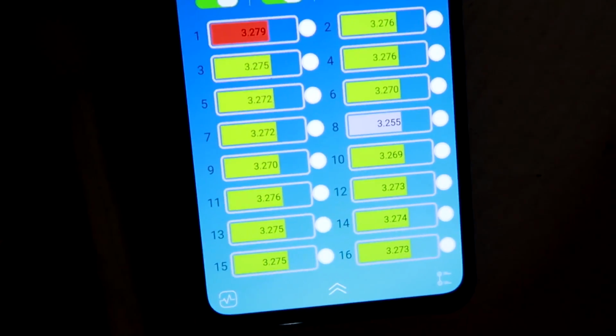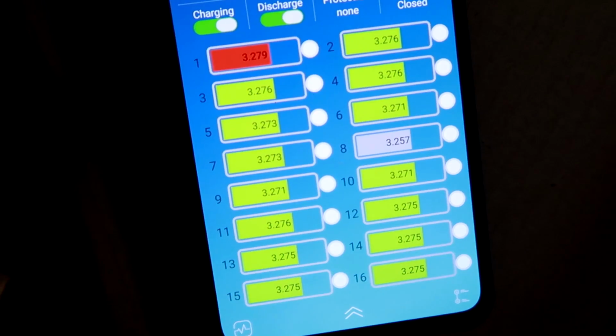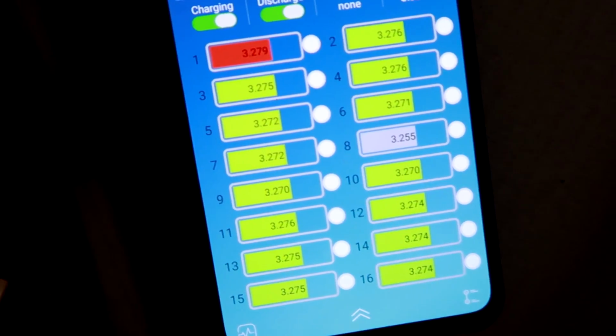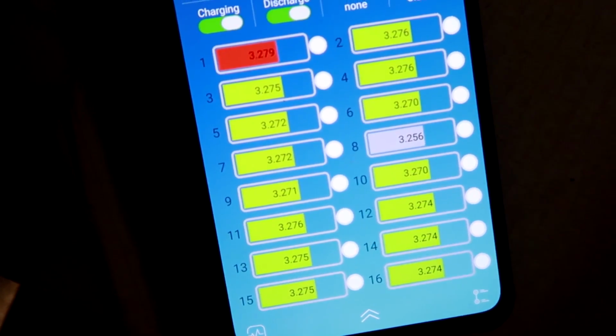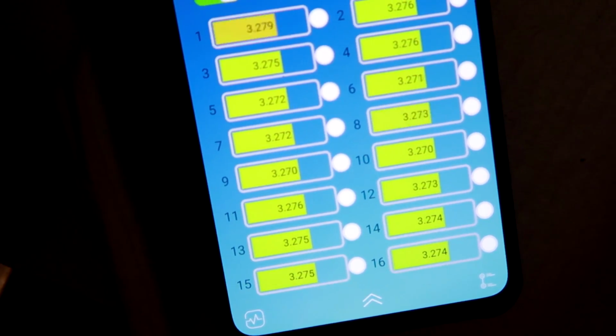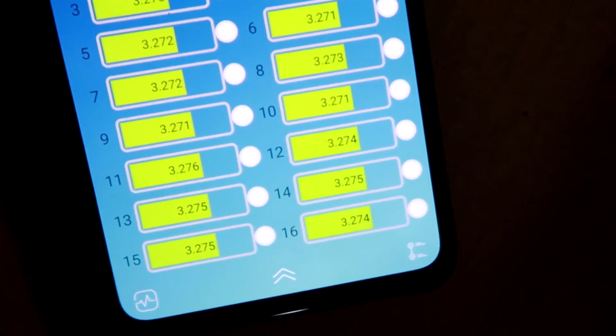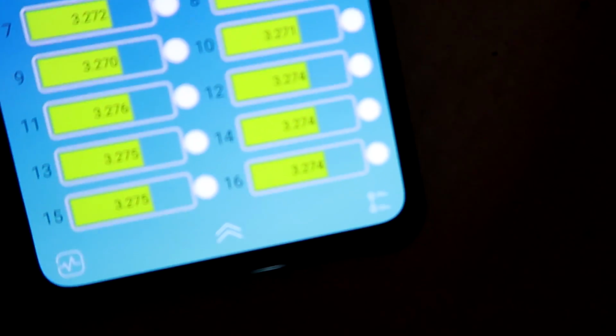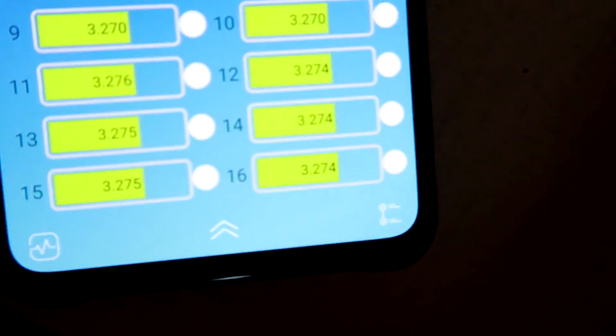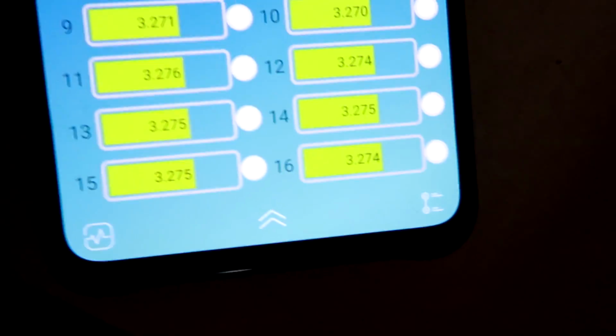I'll show you again, I'll put this next to each other. Watch the number, watch my actual reading, and look at the force I'm applying. Just a tiny bit, bang, look at this, there was 20 millivolts difference. Just me pushing it a little bit further, but it's not actually tightening the nut more, it's more like putting more force on the actual nut, and now it's perfectly fine, in line with all the other ones.